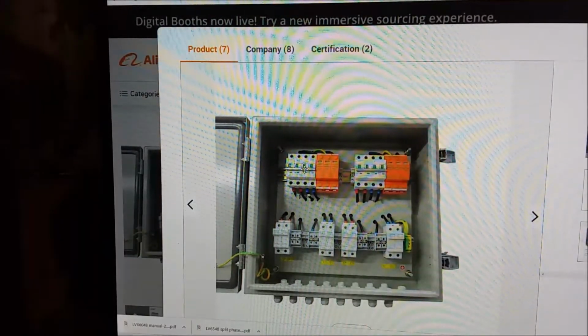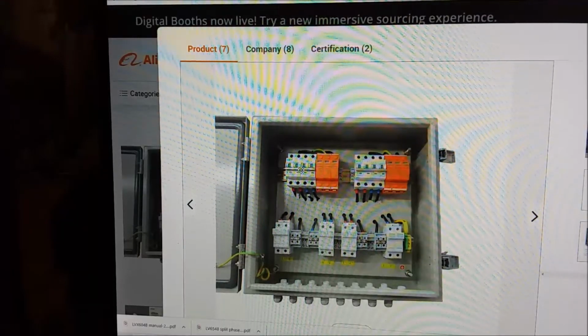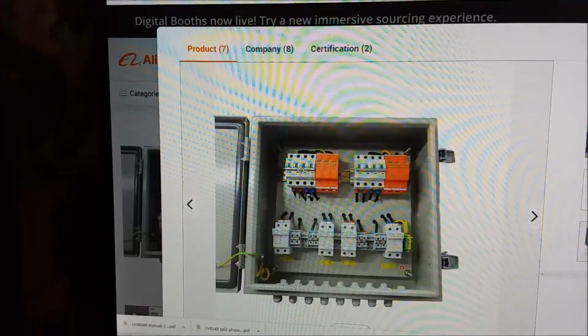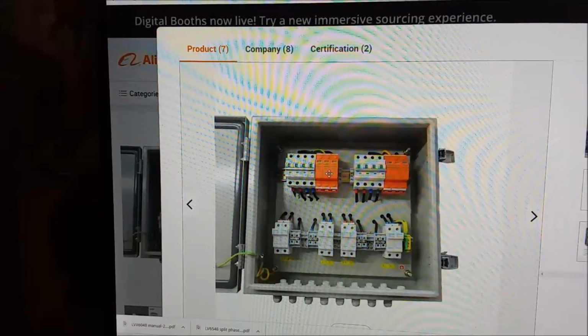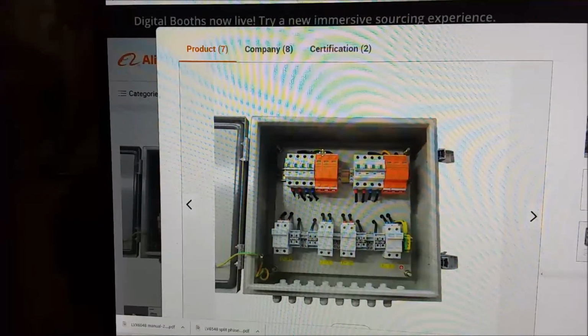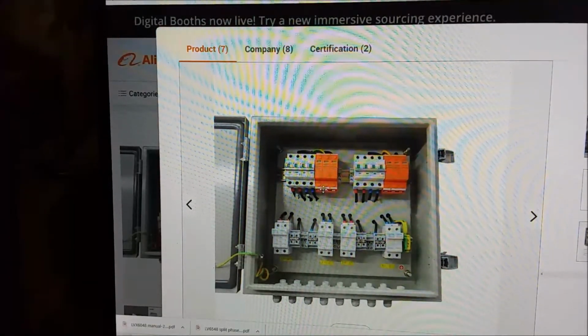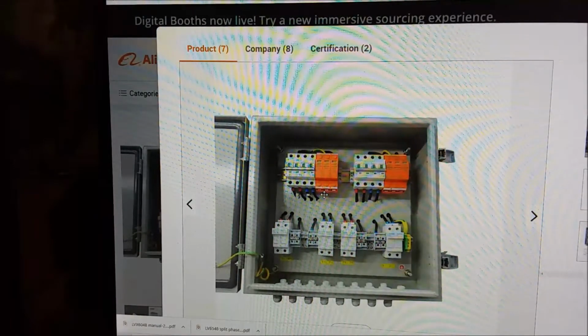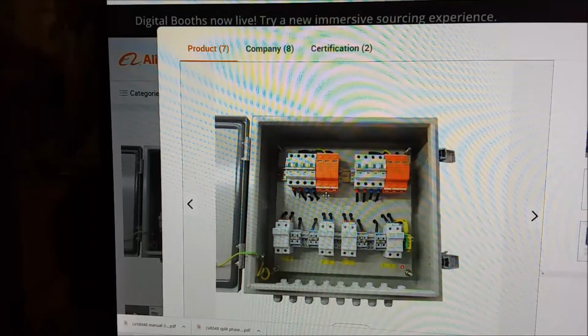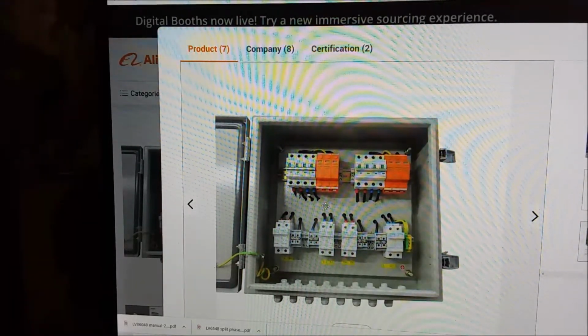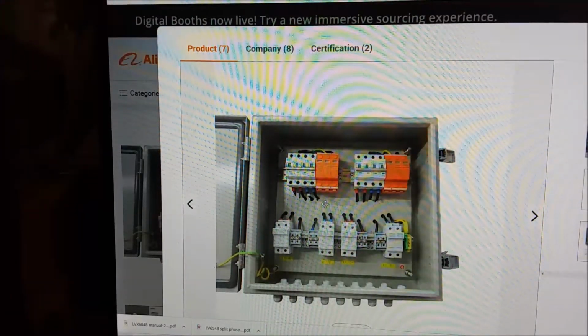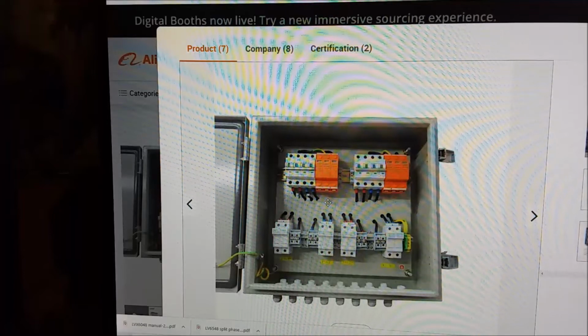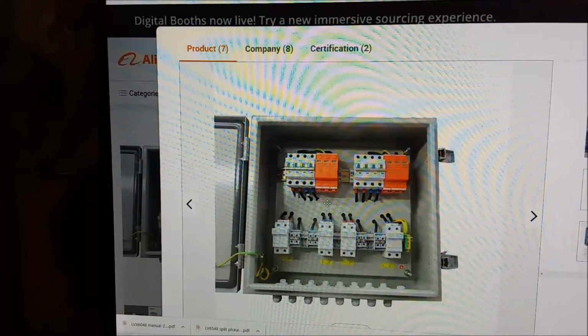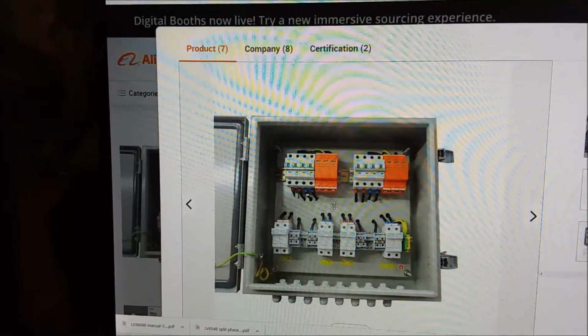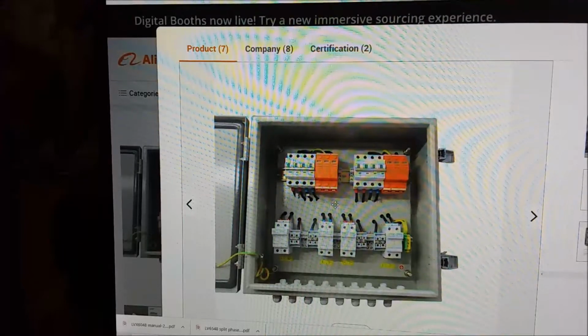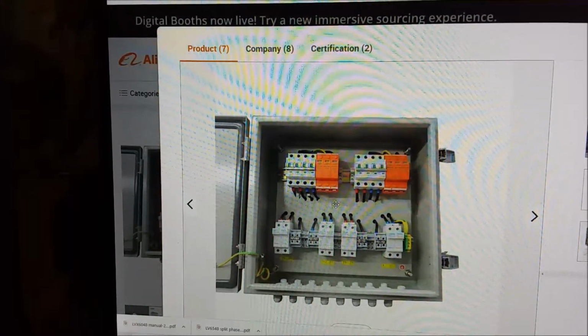Okay, that goes up to circuit breakers, so you come right out of the fuses into circuit breakers in the same box. Now this one has a lightning protector, a surge protector. Rather than just coming out of these circuit breakers, it goes around the top and into this, then you come out of the bottom, and that goes to your inverters eventually. You have to put a circuit breaker between this box and the bottom of the inverter so you can turn it off to work on it, and everybody knows it's off, because we're dealing with really high voltages. I'm going to have 450 volts going into my inverter through this. So you really don't want to put your hand in there — the wattage is high, the amps are high, and the voltage will just plain kill you.